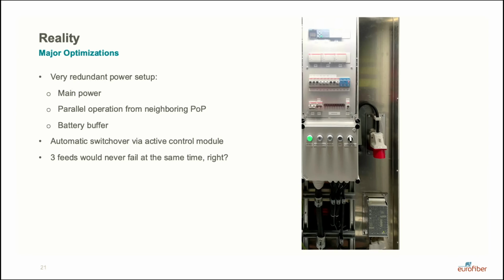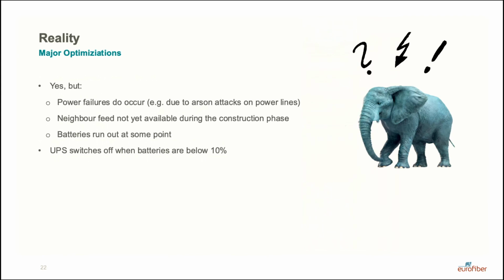To switch between the 2 power feeds, there's an automatic switch control module which is very clever and notices when one power fails and switches to the other, and that works fine. That's basically 3 ways of getting power, and those would never fail at the same time, right? Well, I still think it's a fair assumption, but in reality power failures do occur.